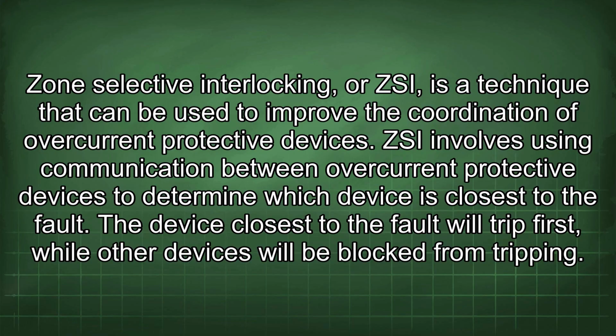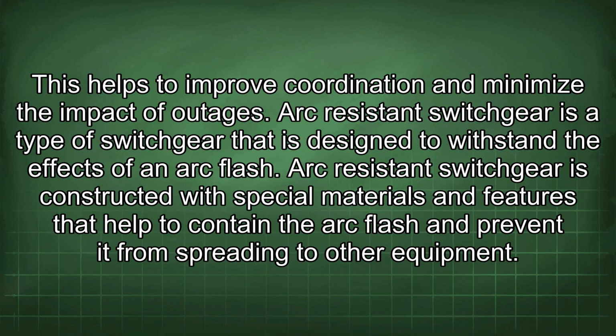protective devices. ZSI involves using communication between overcurrent protective devices to determine which device is closest to the fault. The device closest to the fault will trip first, while other devices will be blocked from tripping. This helps to improve coordination and minimize the impact of outages.